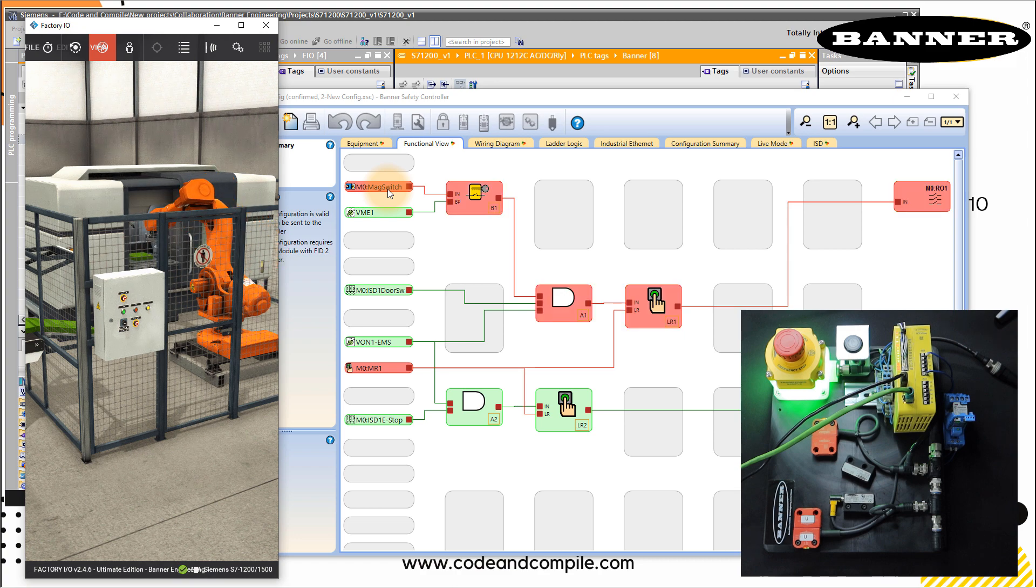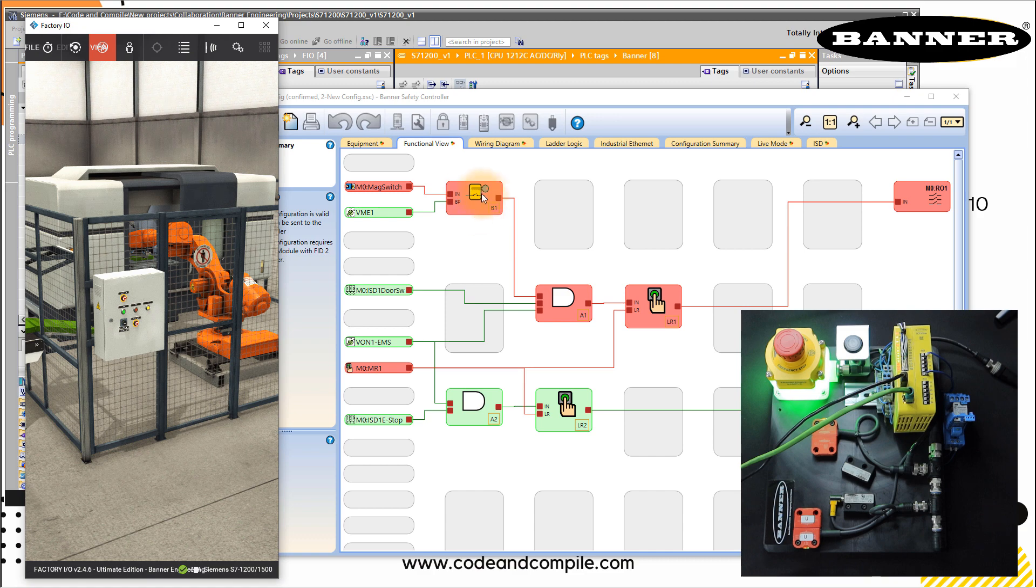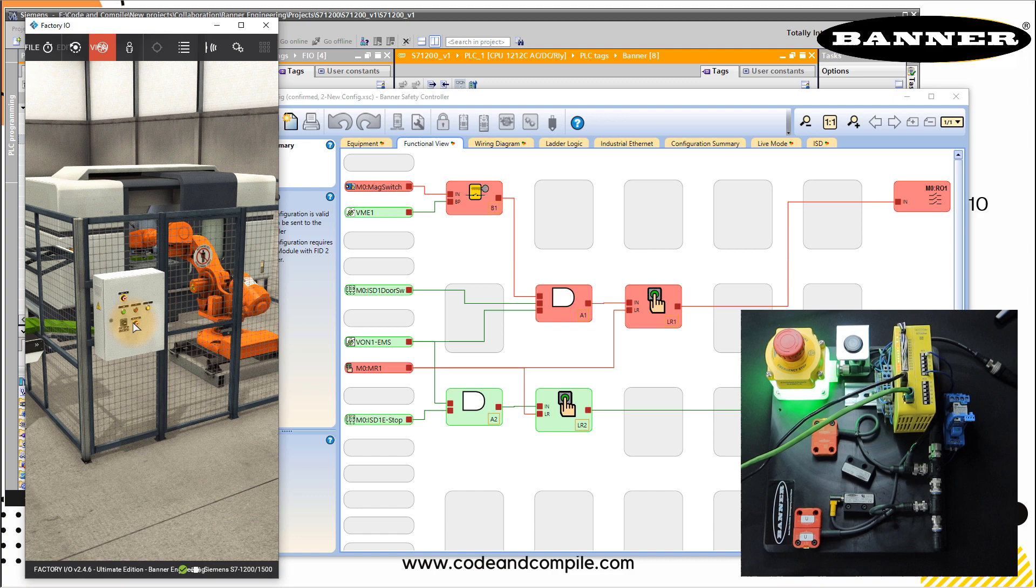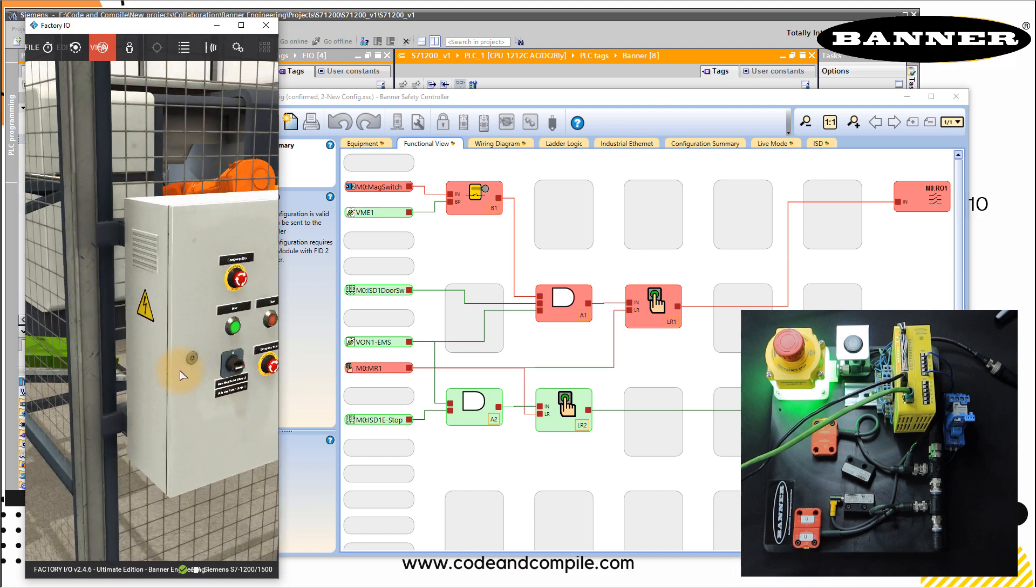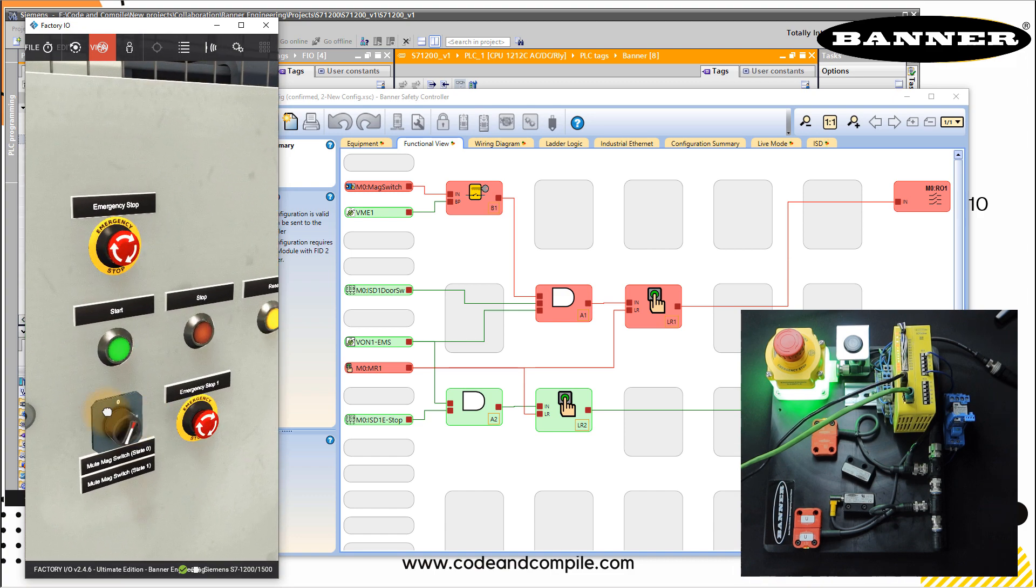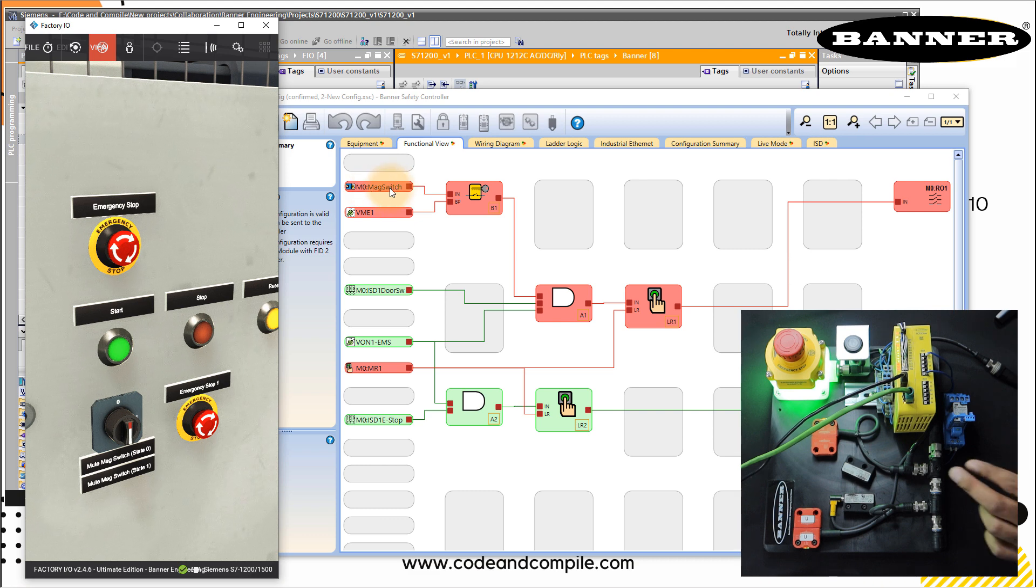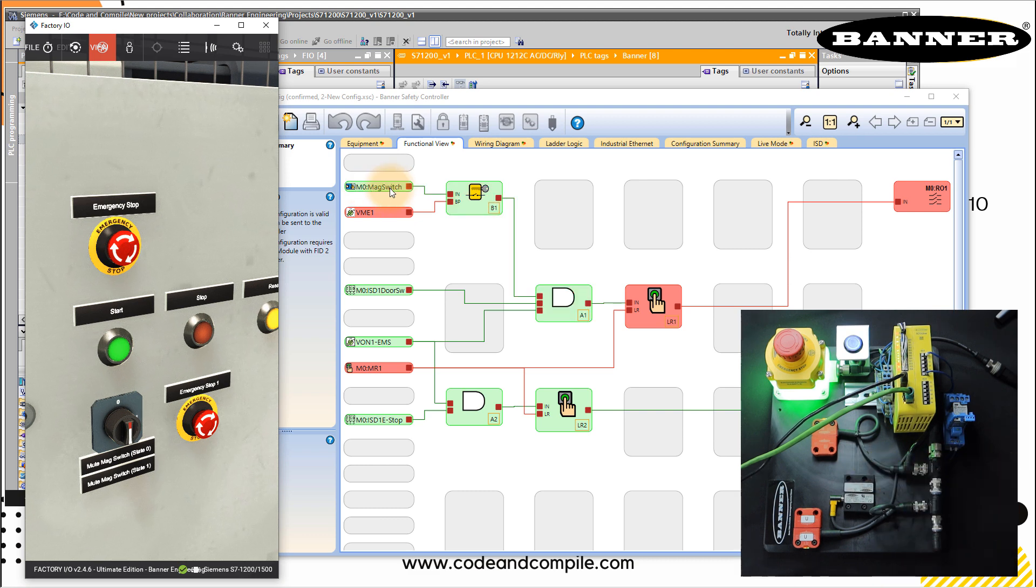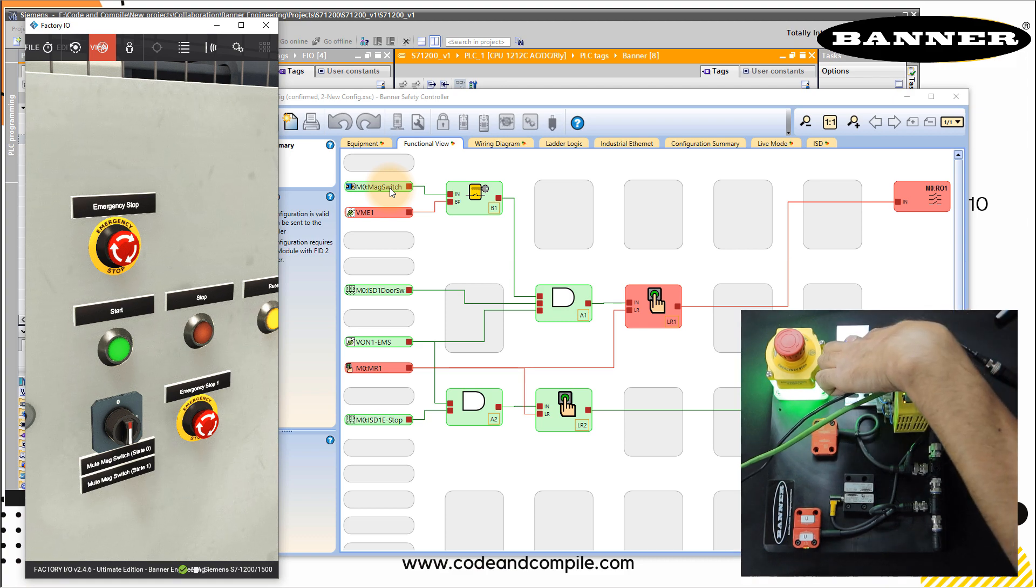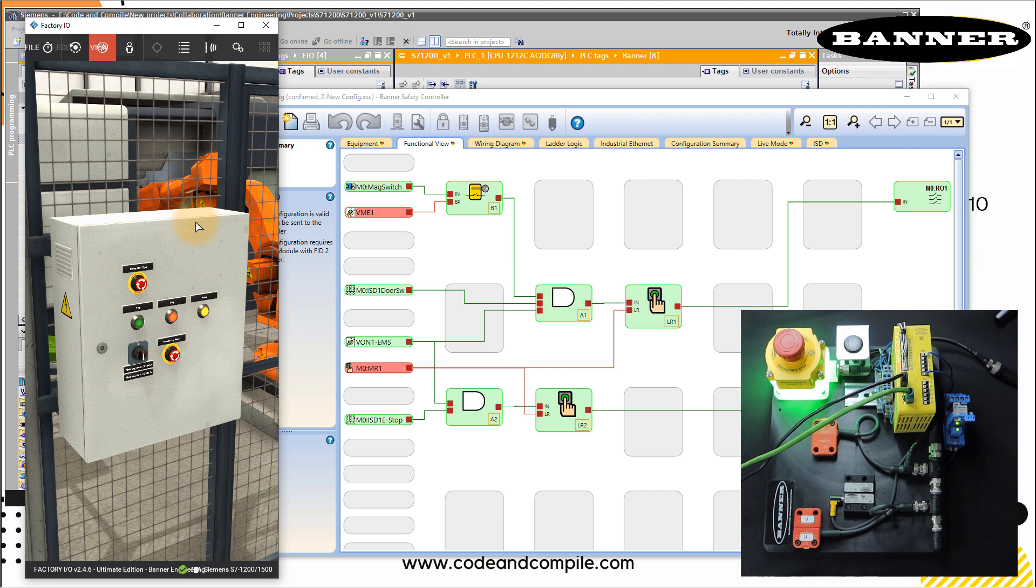Here we go. After one minute, it has turned off my block. And now in this case, what I need to do is I can reset my bypass, bring it back to false and bring back my magnetic switch because my bypass time limit is gone. And now you can see reset operation is required. Reset and the operation starts again.